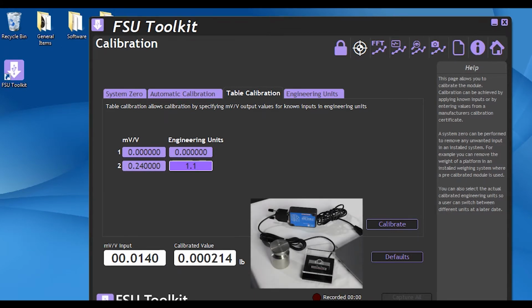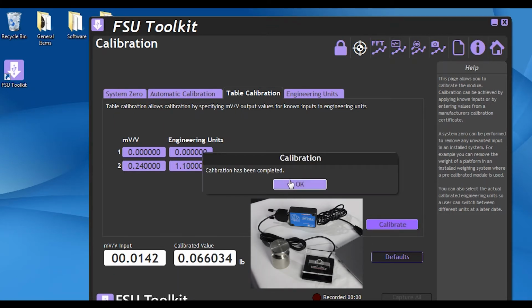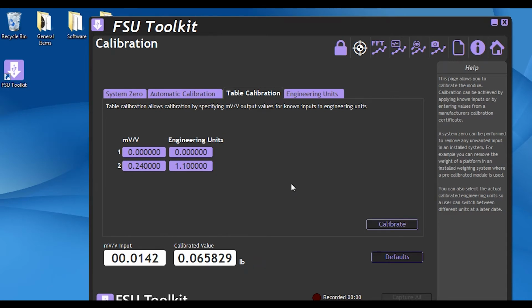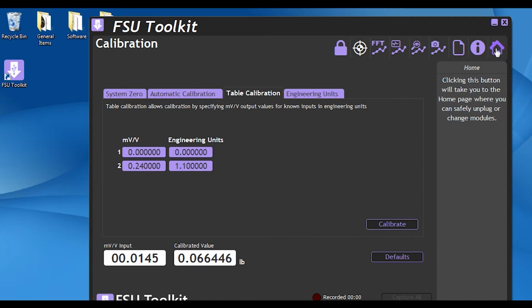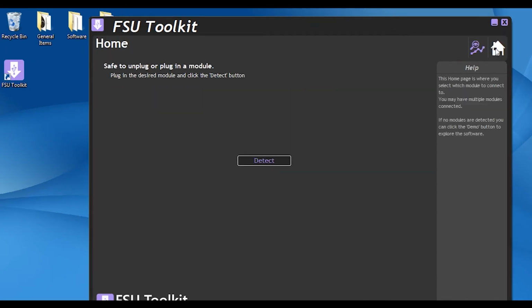The second point that we're going to enter is going to be from the CalCert, and it says that at 0.24 millivolts per volt, the output of the load cell is 1.1 pounds. Once we've completed that entry, we hit this Calibrate button, and it tells us the calibration has been completed. Click OK, and now we're going to go verify that the cal was performed properly by hitting the Home button and then hitting Detect.